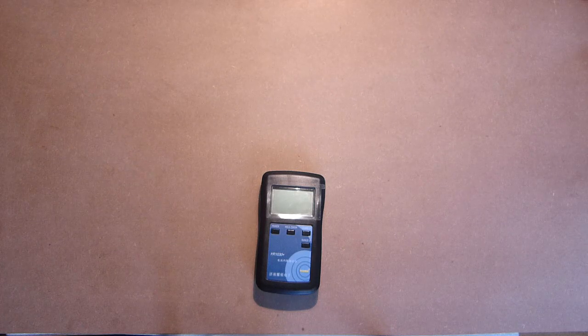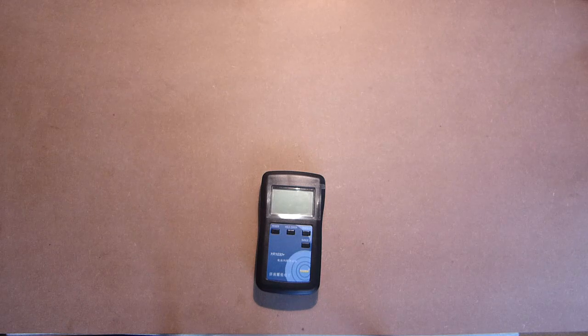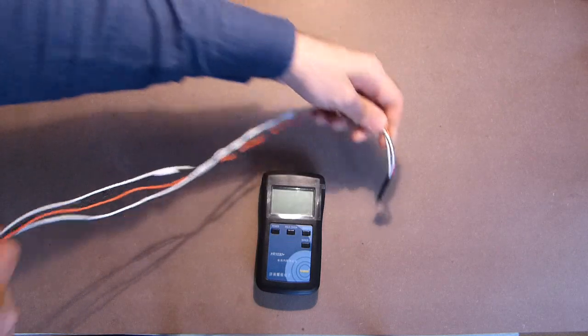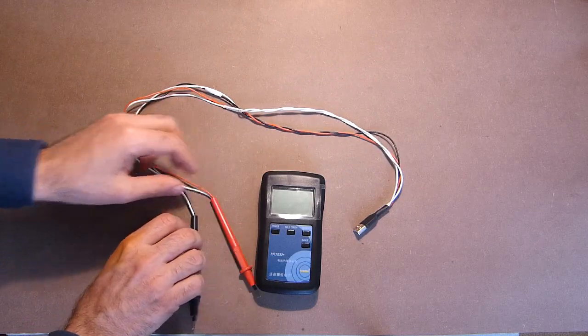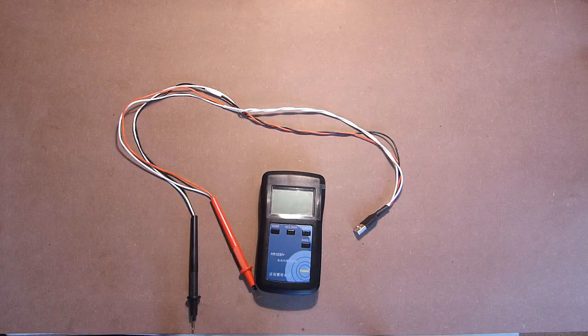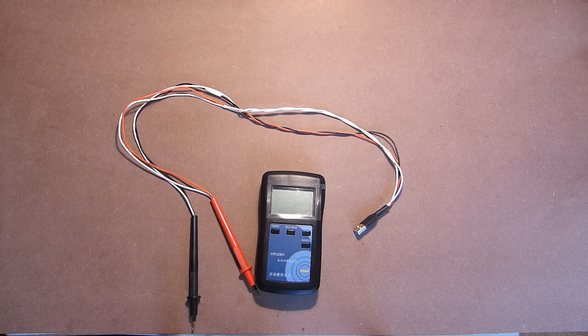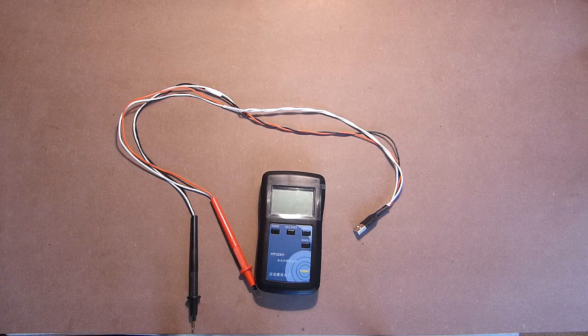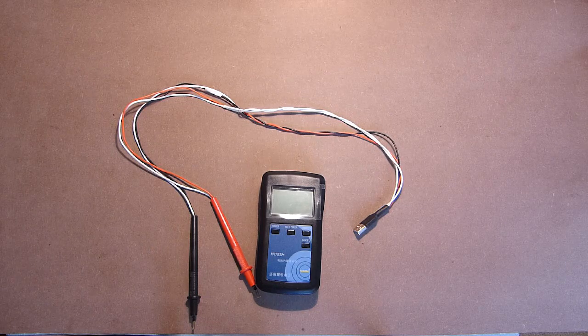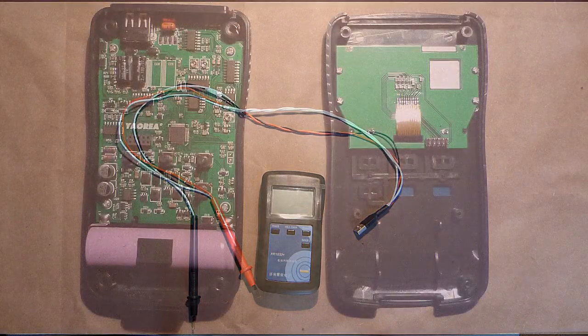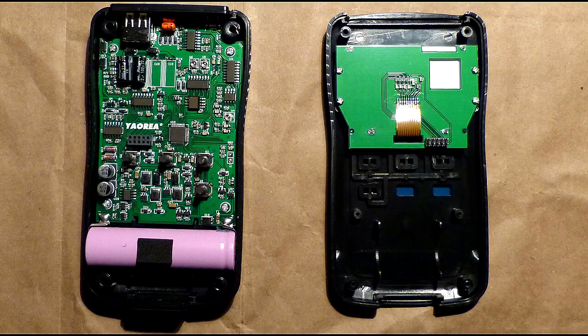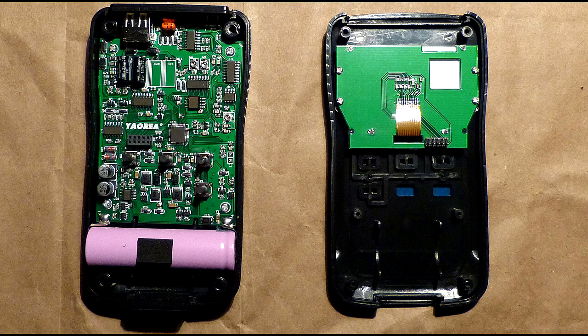Together with this device you can purchase different types of probes, but for my needs I've got the following one. There are lots of rumors on the internet that the probe is very weak to withstand high currents, but in this case high current is not an issue at all. With this probe the device sends the frequency of 1 kHz, receives it at the same time, and this is the only way how this device calculates the internal impedance of a battery.